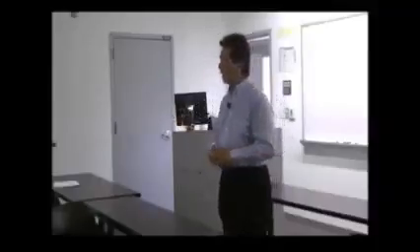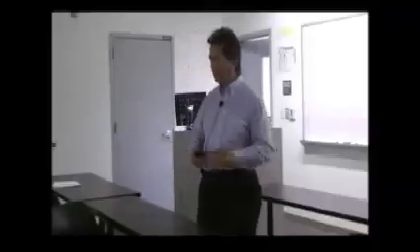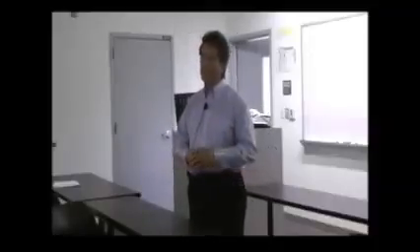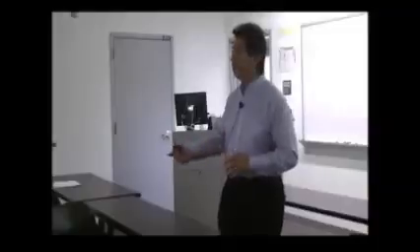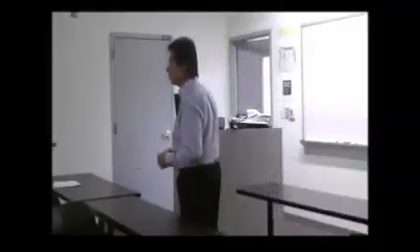Okay. Air handlers, use, type, design and operation, depending on how you're going to use it. I gave you that analogy that the basement used to be a storage, a records, a bunch of boxes. The air handler system in that particular one may have been a 15-ton standard issue air handler. But now we've put people in that. It didn't have heating. It didn't have reheat on that particular unit. It didn't have dehumidification or humidification. It just cooled boxes, right? Just kept that room temperature, say, to 80 degrees. But now we've put folks in there. Now we've got to look at the infrastructure. Can it support the occupants?